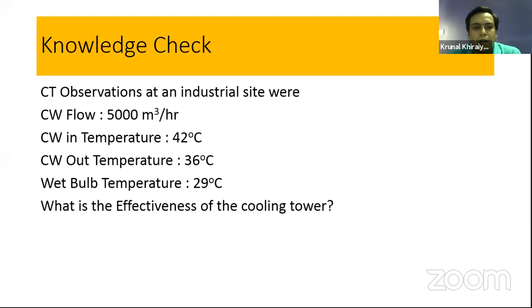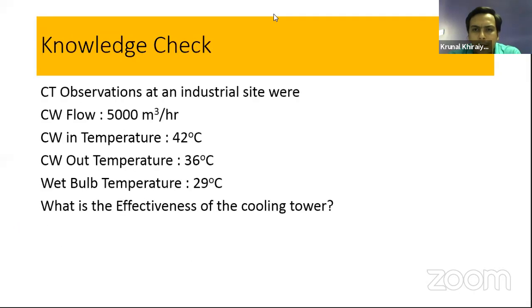Now, knowledge check. Audience, please use the chat box. Here I have taken one observation. The cooling tower observations at an industry site: the cooling tower flow rate is 5,000 meter cube per hour. Cooling water inlet temperature is 42 degrees centigrade. Cooling water outlet temperature is 36 degrees centigrade. Wet bulb temperature is 29 degrees centigrade. What is the effectiveness of the cooling tower? Yes, audience, use the chat box.